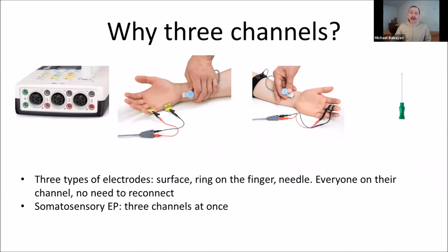And another reason is the recording of somatosensory evoked potentials. If you use, for example, a 2-channel EMG device, it is not enough. Because, for example, if you stimulate in the upper limbs, you have to record the signal from the Erb's point, from cervical, and from cortical, 3 channels at least. And with a 2-channel device, it's necessary to make 2 recordings. It is time consuming and it is painful for the patient. But with the Litebox, for example, you can put 3 channels on three parts of the human body and record 3 channels at the same time.